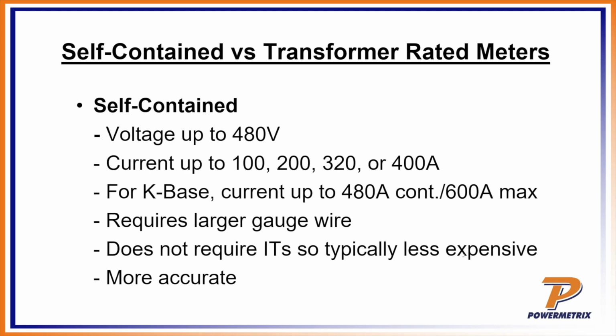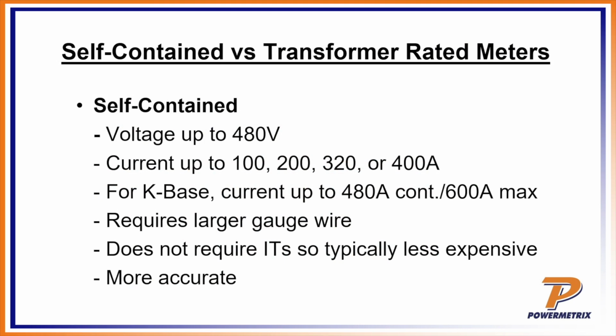But the limitation is on the amount of current, right? Because my CTs, if I have them, are internal in the meter, so I can't do anything to help by adding some external CTs or anything to it. So I'm very limited in how much load I can handle. But they do tend to be less expensive to install, and they tend to be more accurate. Okay.